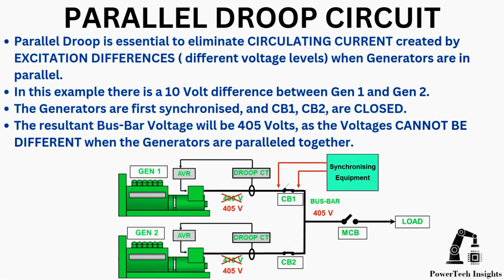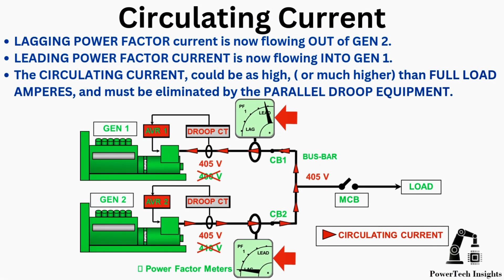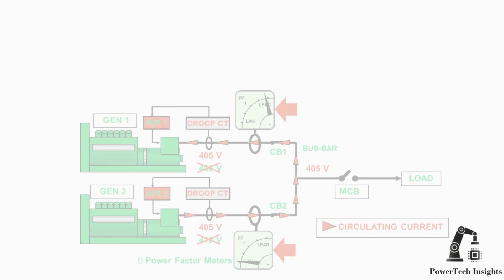Parallel droop circuit. Parallel droop is essential to eliminate circulating current created by excitation differences and different voltage levels when generators are in parallel. In this example, there's a 10-volt difference between Gen 1 and Gen 2. The generators are first synchronized and CB1, CB2 are closed. The resultant bus bar voltage will be 405 volts, as the voltages cannot be different when the generators are paralleled together. The circulating current could be as high or much higher than full-load amperes and must be eliminated by the parallel droop equipment.